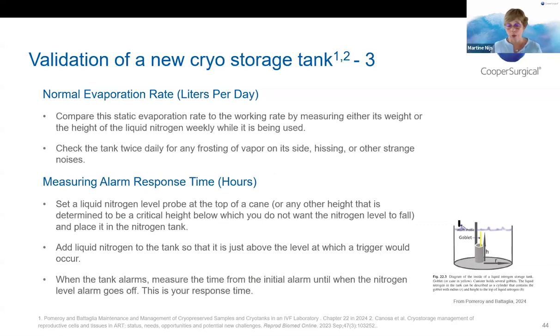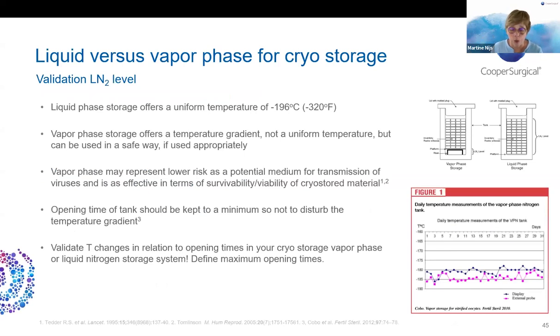The alarms are also very important. You have to check and validate if your integrated alarm is working. That means you need to add an extra alarm and then create an alarm situation. Leave the tank open, for example, and see if the external new alarm and the alarm that is sitting in your tank correlate, and whether they alarm when there is a problem.